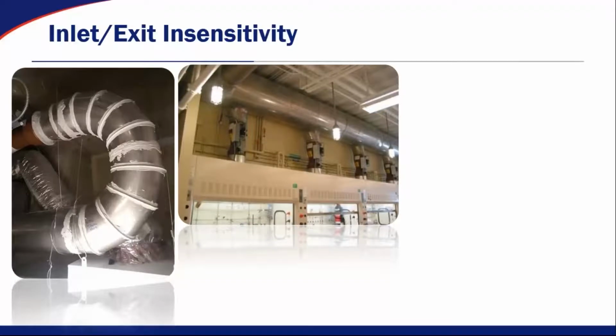Here's another challenging installation where you have valves mounted vertically directly off of fume hoods. And in this particular application, there's such a short run of duct between the fume hood and the main exhaust riser, there's absolutely no way that you could put a flow sensor in there and get any relative accuracy to control that airflow.